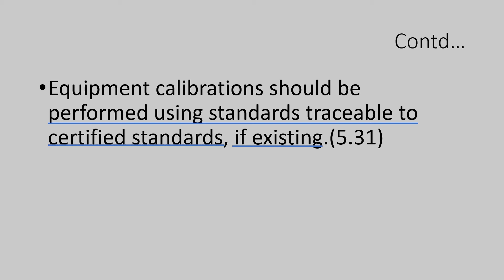The calibrations have to be carried out using a traceable certified standard. What is a traceable certified standard? It is the standard that has been used for calibrating the internal equipment, certified by a competent authority. For example, how are time zones calibrated for each country? It is not decided in vacuum — there should be a traceable standard based on which it is decided. It is GMT. The GMT is considered as zero time, and all others are calibrated according to the rotation of Earth with respect to the Sun. So GMT is considered as a traceable standard.